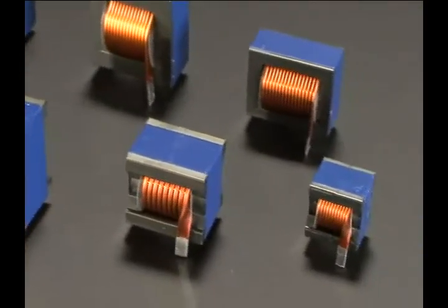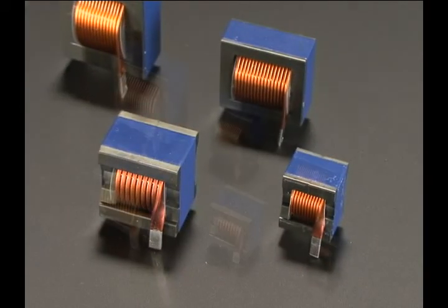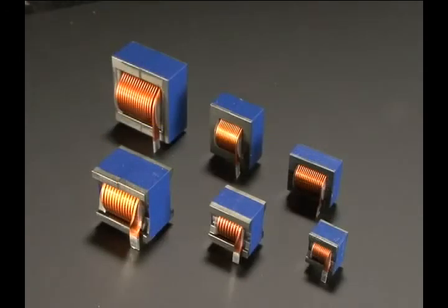Coils are found in the motors of seawater and freshwater pumps, and their insulation is weakened by the absorption of moisture. The main purpose of measuring insulation resistance using a Megger is to check for coil insulation degradation.